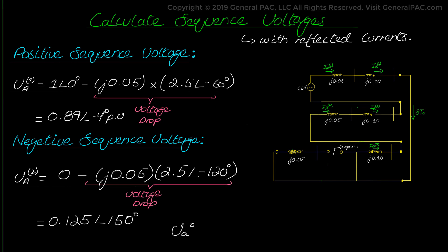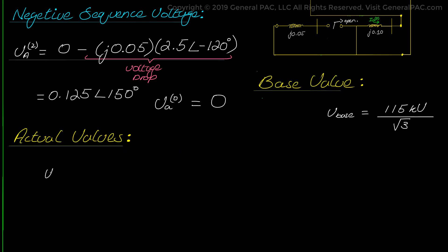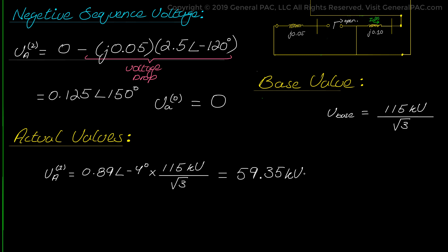Zero sequence voltage will be zero because the zero sequence current was also simply zero. We need to set up a base value to convert the per unit voltages to actual line-to-ground voltages. V-base can therefore be taken as 115 kV over the square root of 3. Multiplying the components with the base value, we get the values as shown below. The positive sequence voltage is equal to 59.3 kV at angle negative 4 degrees.